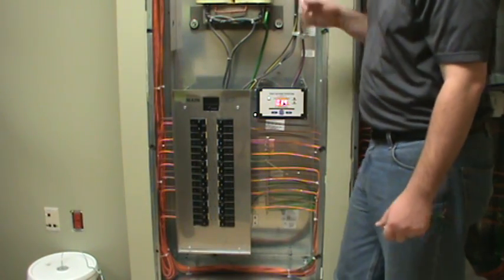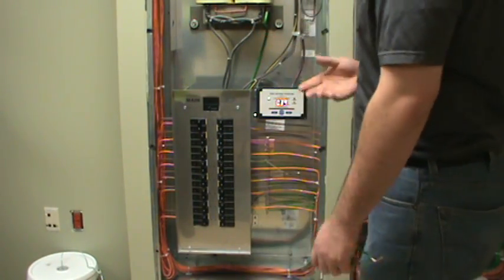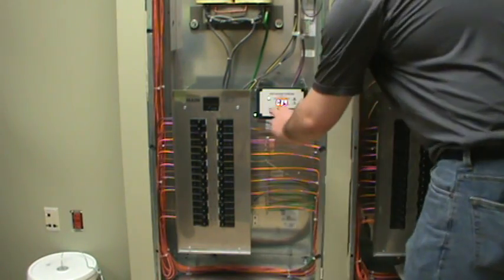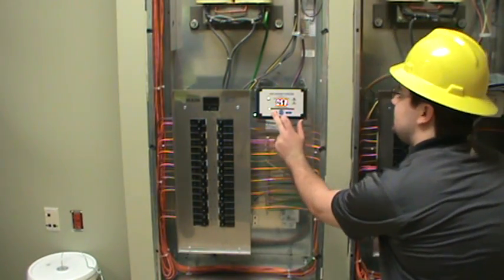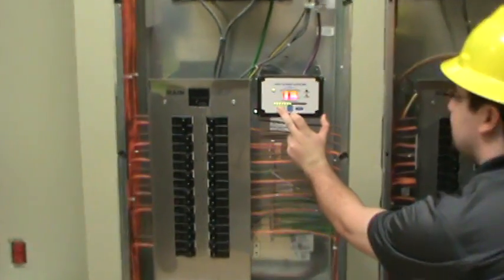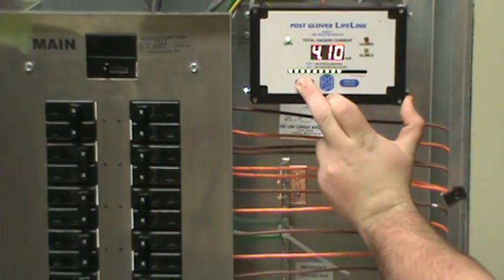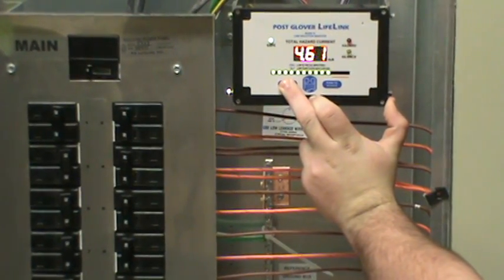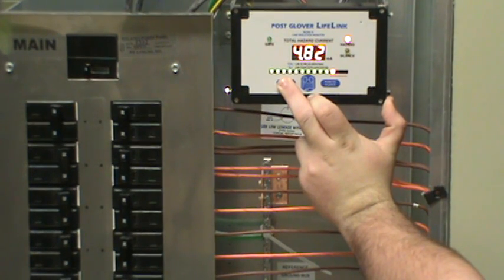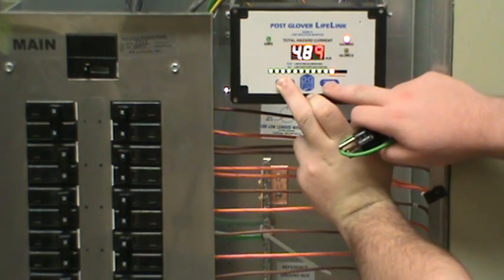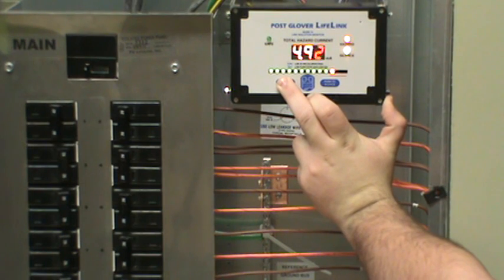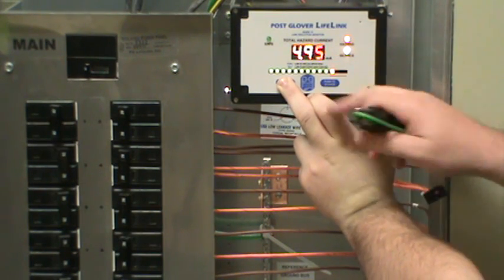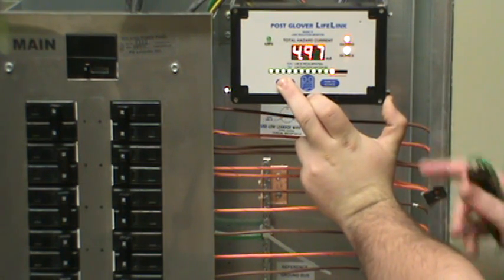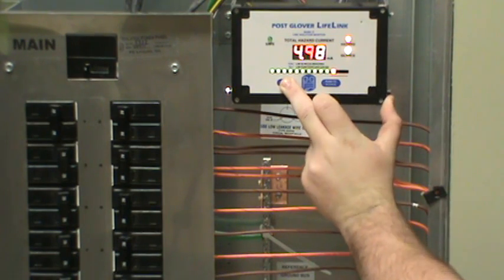You can actually test this yourself, which is required by code to do once a year. Fairly simple. All you have to do is hold this push to test button. You'll see that current go up. We'll get an alarm at 4.8. That green safe LED is going to go off. The red one's going to come on. Go ahead and tap silence where you got that button pushed in. You'll see the safe go off, the alarm went off, and our silence light goes on.